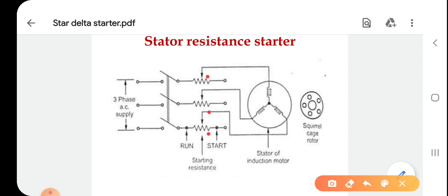The reduced voltage gets applied to the stator, which reduces the high starting current. Whenever voltage is applied, the reduced voltage decreases the starting current. As the motor starts running, the resistances are gradually cut off from the stator circuit. When the resistances are removed from the stator circuit — that is, the rheostat is in the on position — the rated voltage is applied to the stator and the motor runs at normal speed.